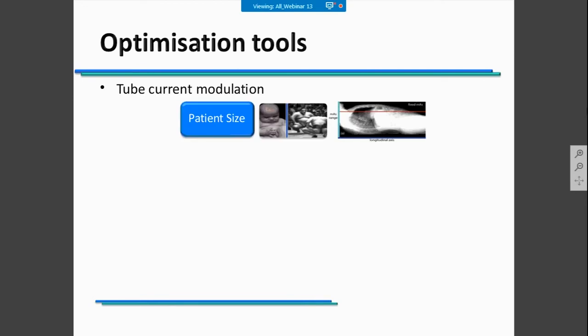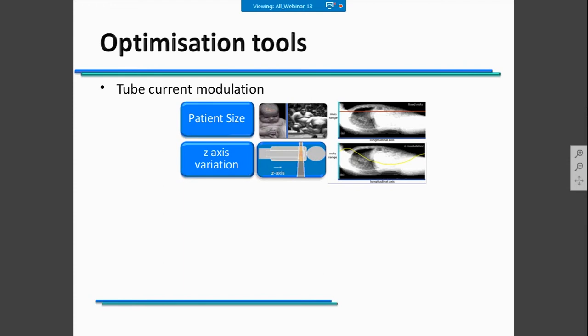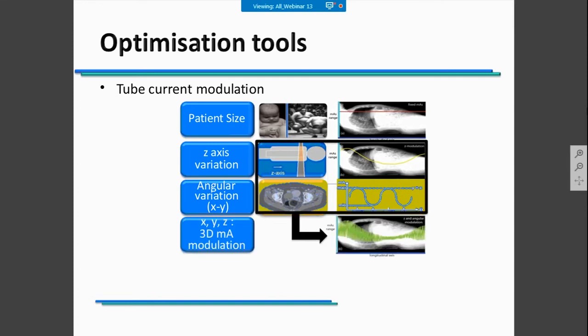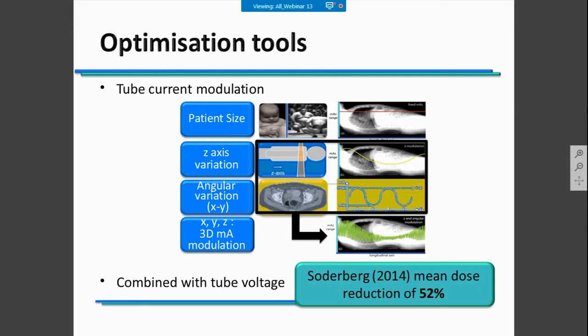The most well-known optimization tool is tube current modulation. It also depends on the type of CT scanner you have. It could be based on patient size, on z-axis variation, on angular variation, or it could combine z-axis and angular variation together simultaneously, decreasing the dose in your examination. If you have a CT scanner that can combine current modulation and voltage modulation at the same time, you are going to have a dose reduction of more than 50%. So it's important to be aware—if you have this technology in your scanner, you must understand how it works and pay attention to its settings.